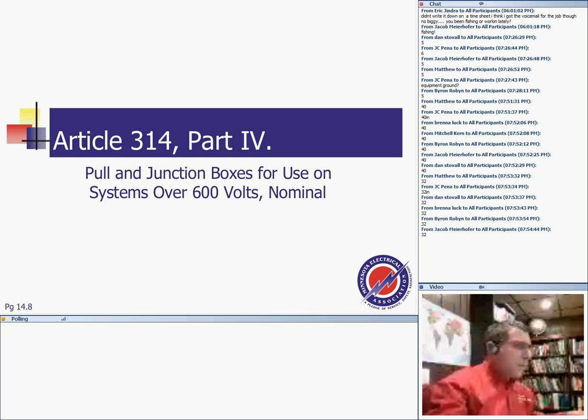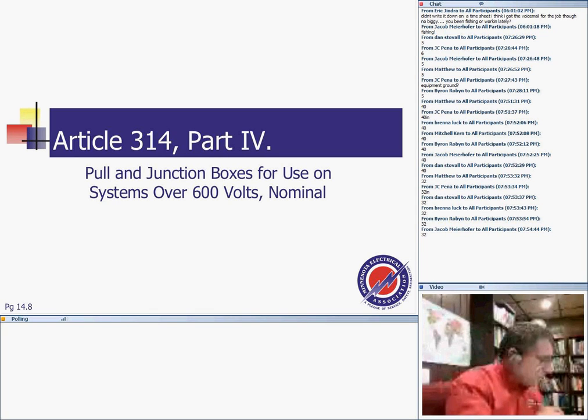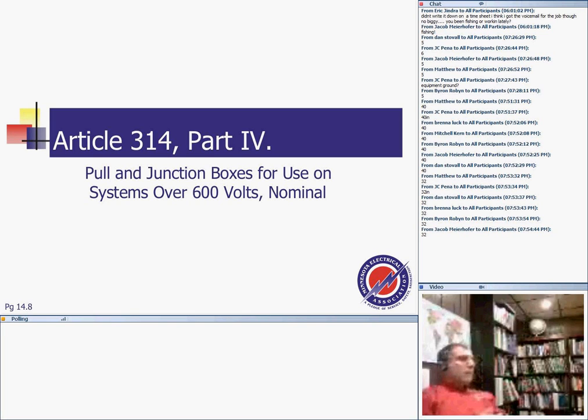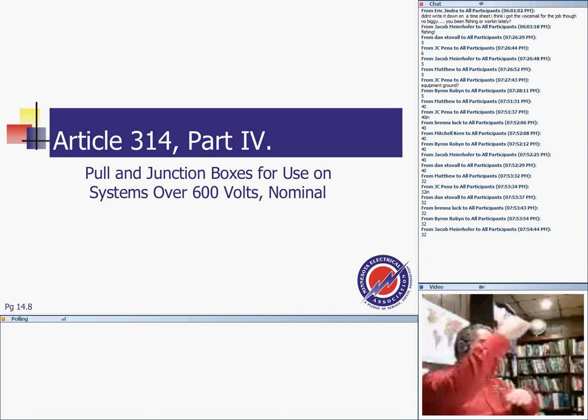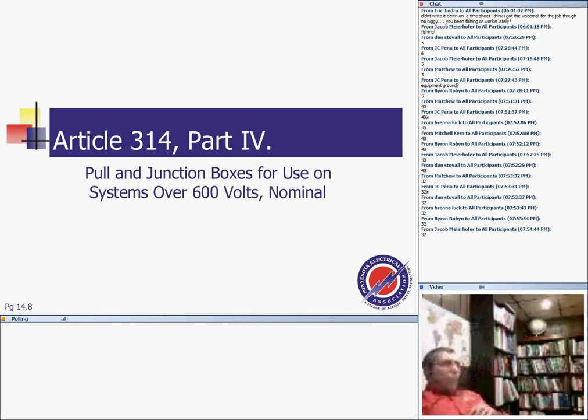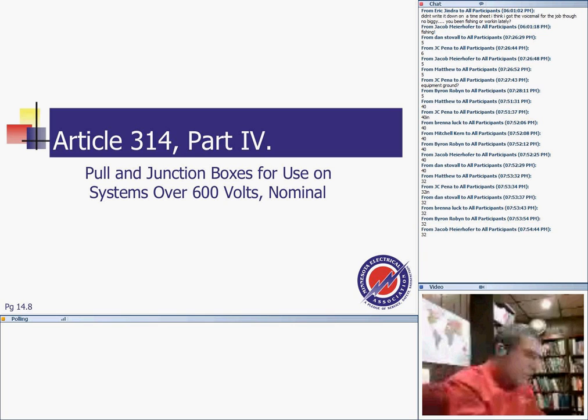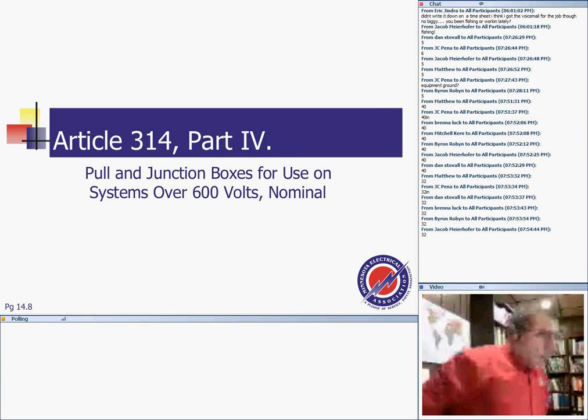Any questions, guys, before we move into high voltage pull boxes? To summarize, especially for pull boxes, we see a straight pull is 8 times the largest conduit. Angle, 6 times the largest conduit plus all the other conduits sharing the same wall. U pull, same thing: the distance from where the conduits enter the wall to the opposite wall is 6 times the largest conduit engaged in the U pull plus the conduits sharing the same wall with the U pull.